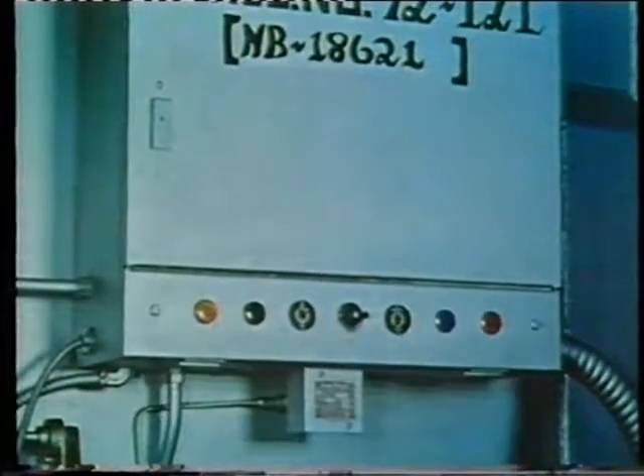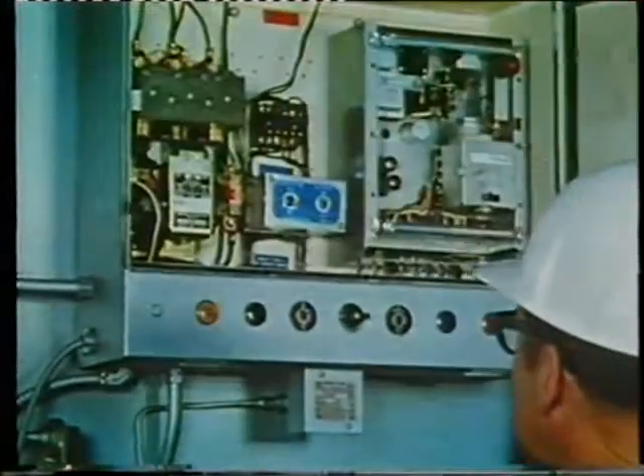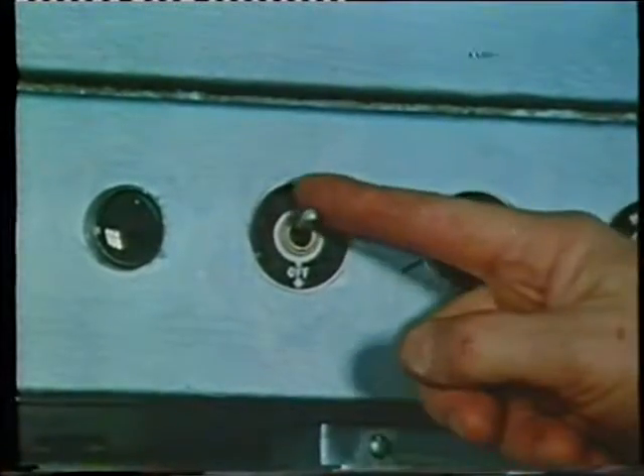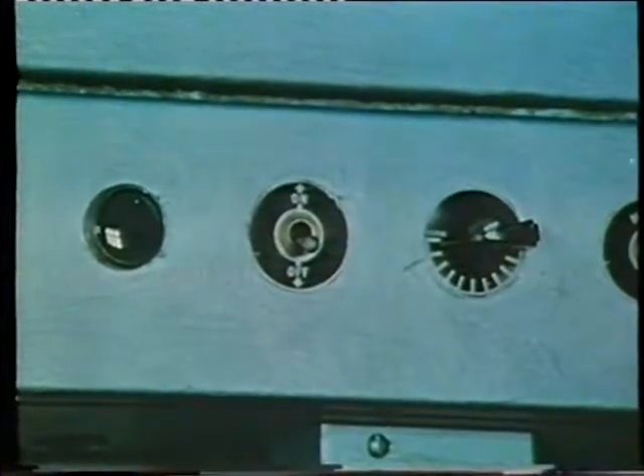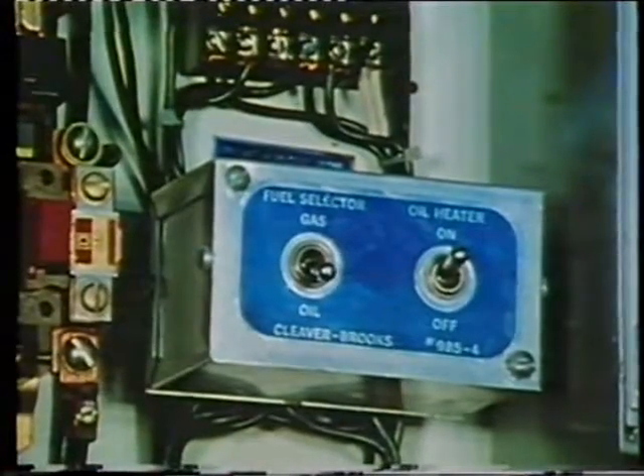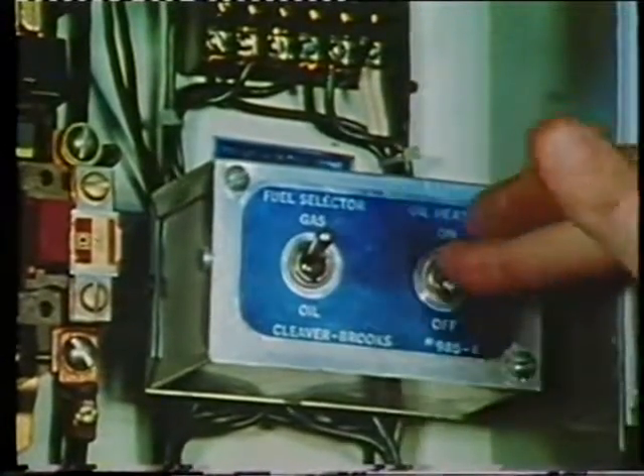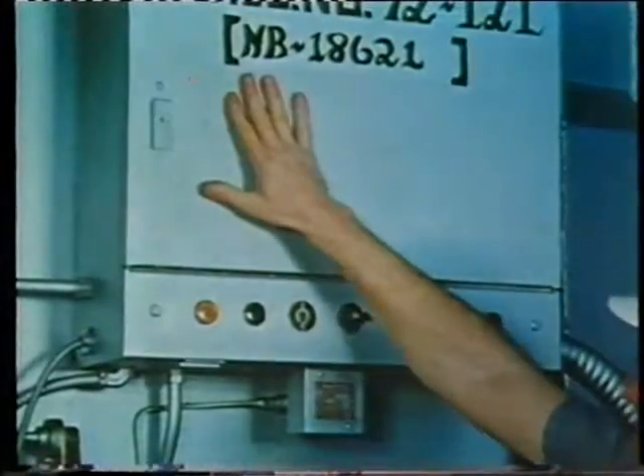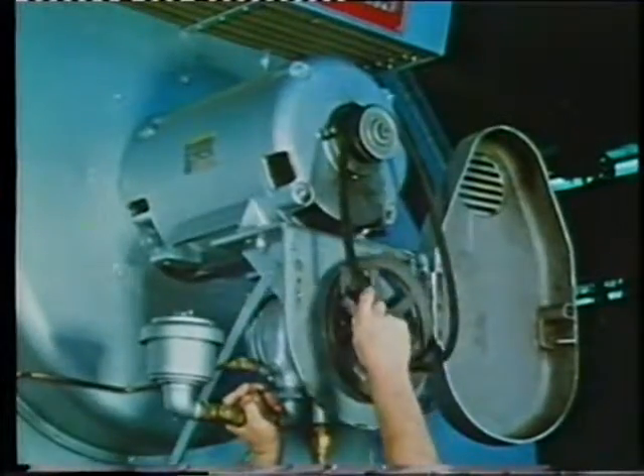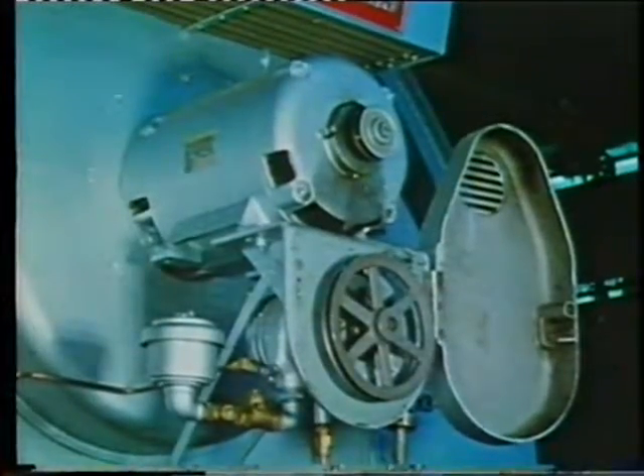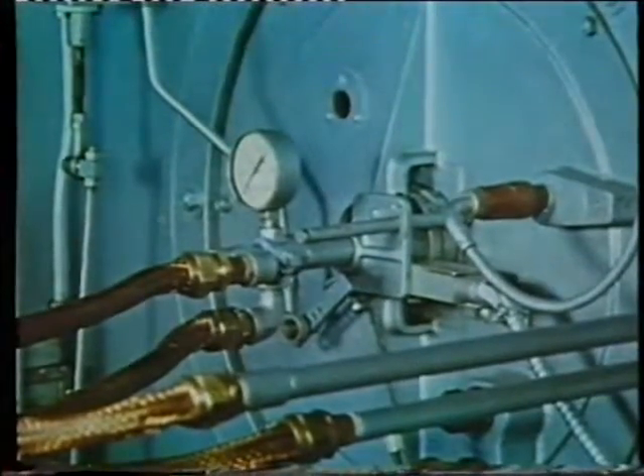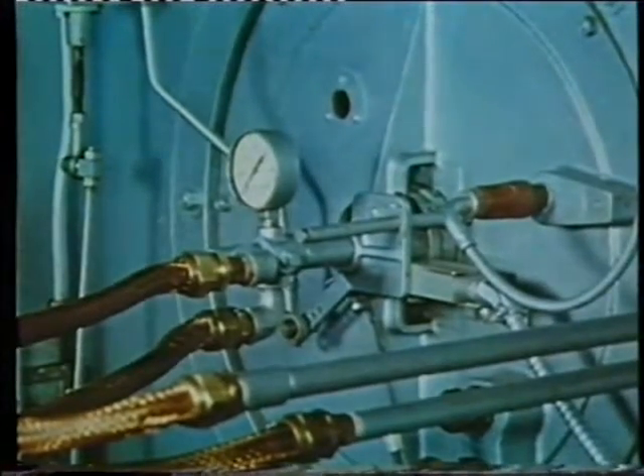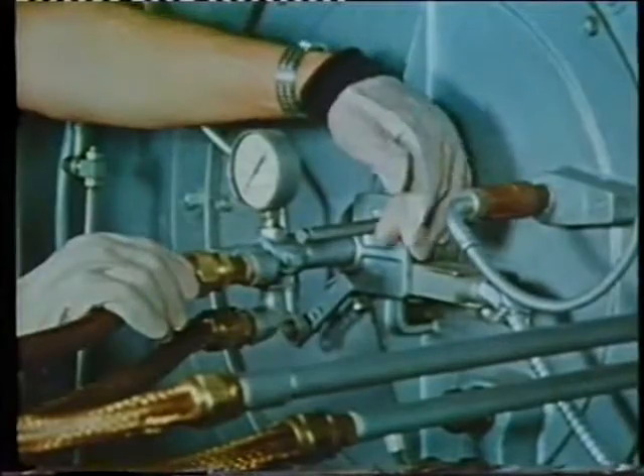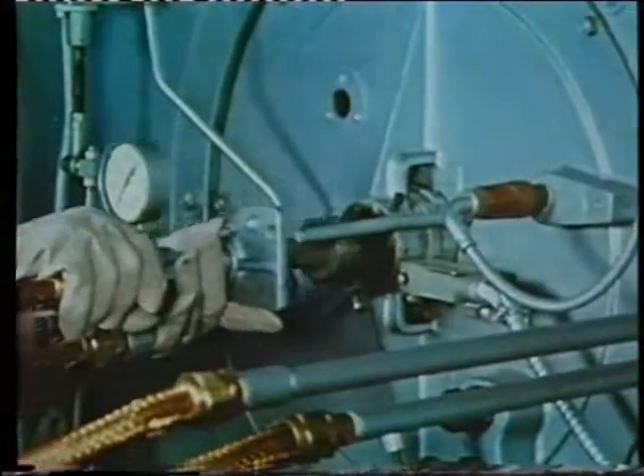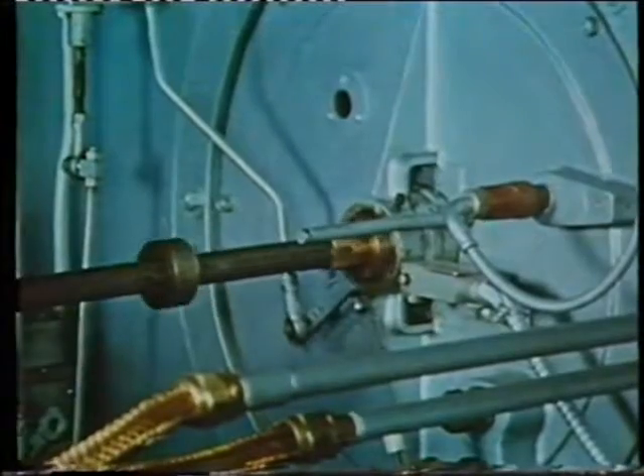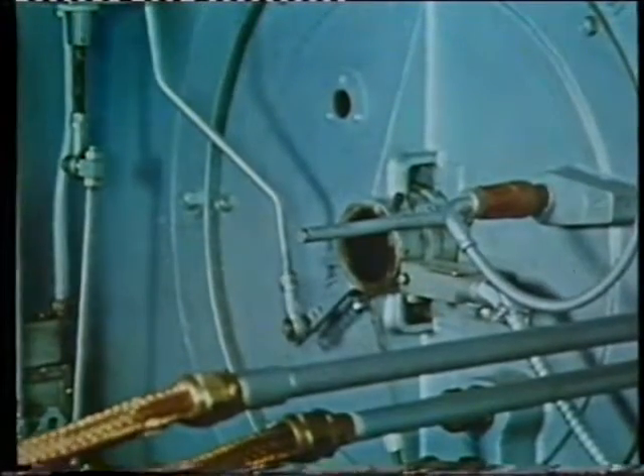To change from oil to gas on a dual-fuel boiler, a specific sequence is followed. The fireman turns the control switch to the off position. The fuel selector switch is set for gas, and the heater switch is turned off. The belt is removed from the atomizing air pump, and the burner is withdrawn from the boiler, making certain all oil is drained and the burner is clean. On some boilers, the burner unit is not completely removed, but is simply pulled back and locked in the inoperative position.